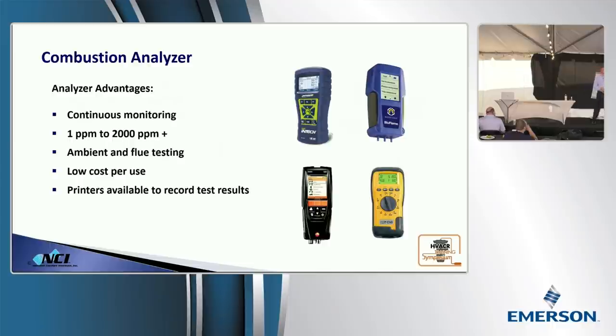I don't care what test instrument you use for combustion analyzers. I really don't. We've got multiple brands up there. It needs to do three things. If it does these three things, it's all I care about. I don't care what the name is, what color it is. It needs to do carbon monoxide, oxygen, and flue temperature. If it does those three things, it's great. If it only does oxygen and temperature, it's useless.